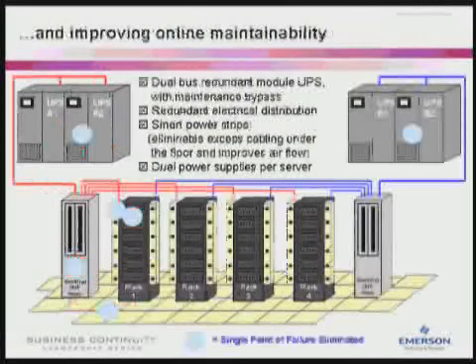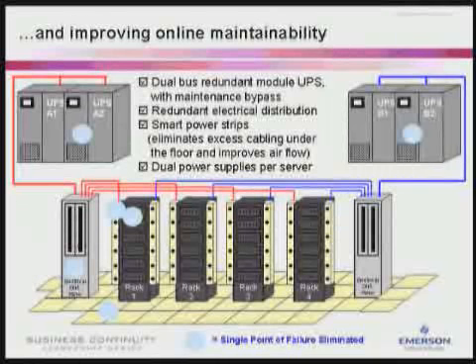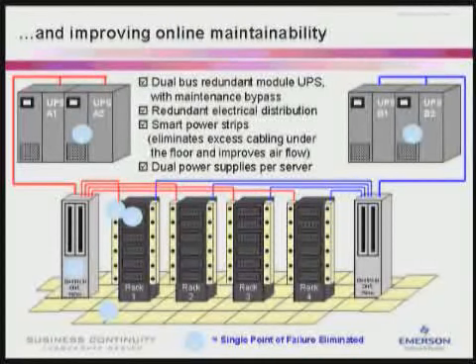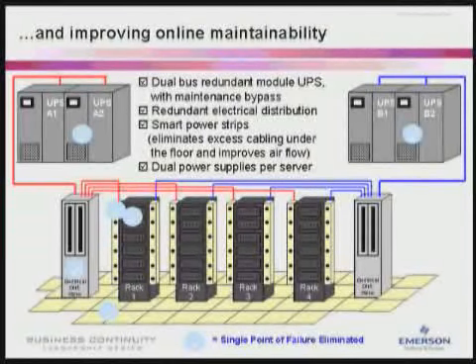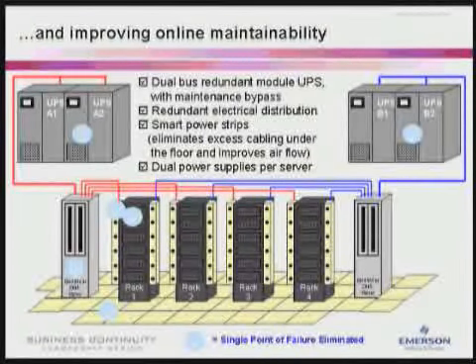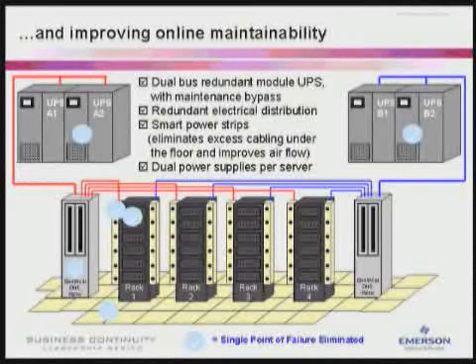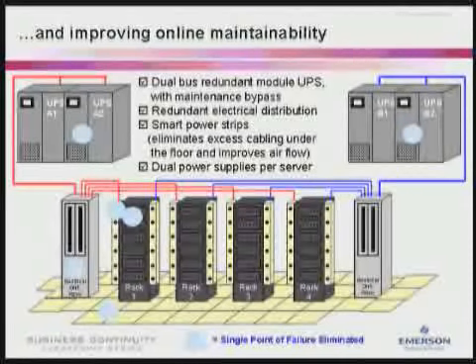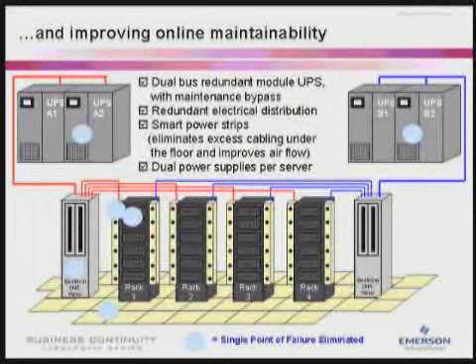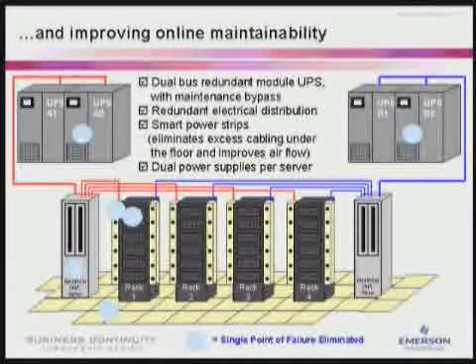Moving to a fault-tolerant data center, we've added a dual bus redundant module UPS with maintenance bypass, redundant electrical distribution, smart power strips in the racks. These help to eliminate excess cabling under the floor and improve airflow, and dual power supplies per server. All single points of failure are eliminated except for EPO and the fire systems.